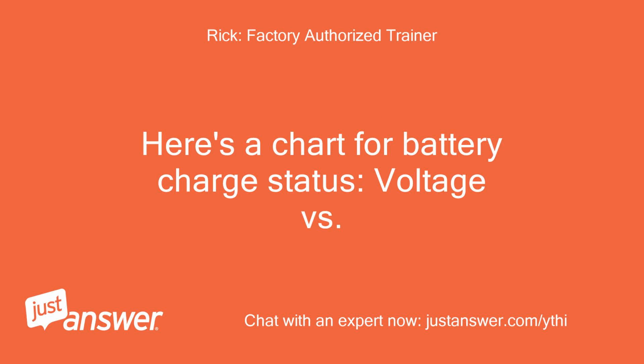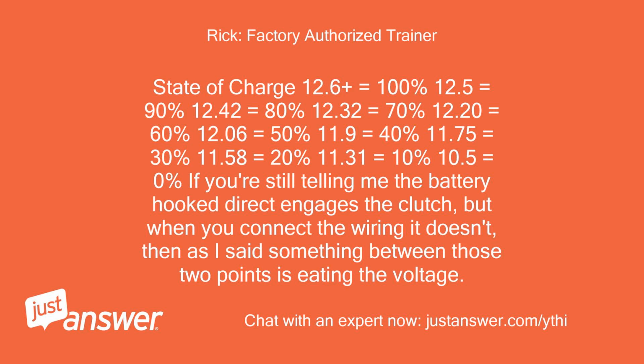Here's a chart for battery charge status, voltage versus state of charge: 12.6 plus equals 100%, 12.5 equals 90%, 12.42 equals 80%, 12.32 equals 70%, 12.20 equals 60%, 12.06 equals 50%, 11.9 equals 40%, 11.75 equals 30%, 11.58 equals 20%, 11.31 equals 10%, 10.5 equals 0%.